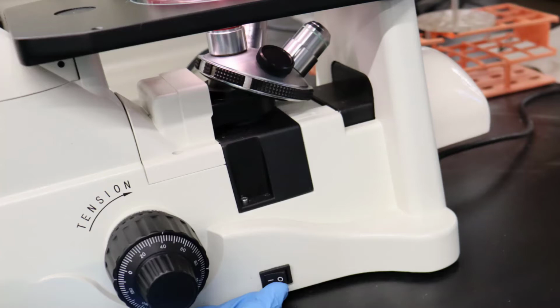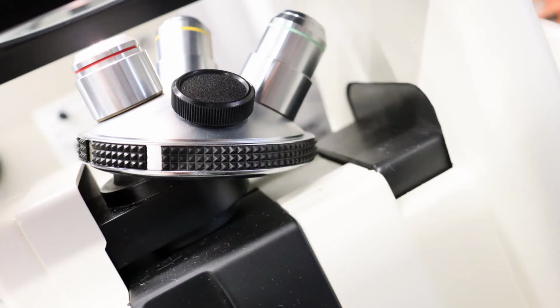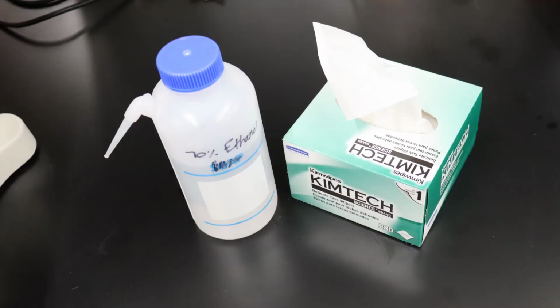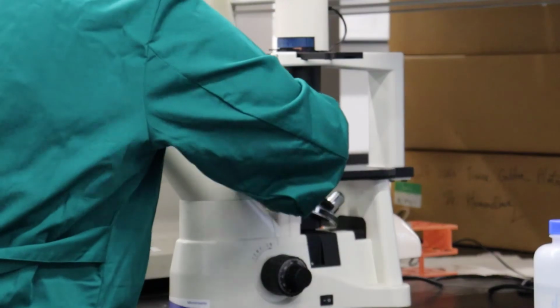This one has a little bit of a delay, but you should wait, and then you should see the light coming through the objective. Just like the microscope is stored always with the cover on to prevent dust from getting in the objectives, it should also always be set on the lowest objective possible. So here we have it on the lowest or shortest objective. It's usually lined with red compared to the other ones, which are yellow and green here. So it should start at the lowest magnification, the smallest objective. So just like I covered the counter with ethanol, I'm going to spray the stage, again to make sure it stays contaminant free. So just a small bit of 70% ethanol and a Kimwipe.